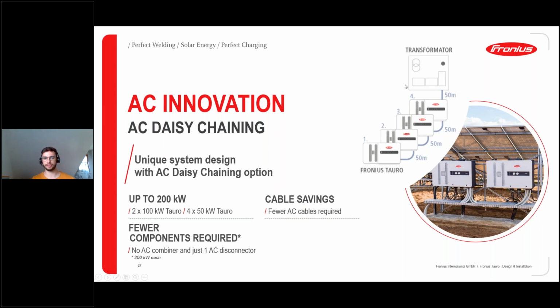And in total, what we do here is, of course, save a lot of cables because we don't need to run the full length to the main distribution frame every single time. And also we save a few components. If you think about it, you do have a code in your region, for example, which states that you have an AC disconnector on every component that you install, on every inverter. So if you would singly cable every single inverter to the main distribution frame, you would need 4 AC disconnectors per line. And in our case, we only have one line here to the main distribution frame, and we can set one centrally positioned AC disconnector in this line and save 3 AC disconnectors in that regard. So we do not only save cable costs on cable length, but we also save on components required. So yeah, this is called the AC daisy chaining option, and you can order it as an option.